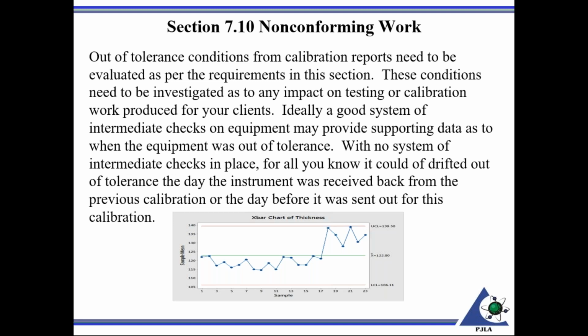for this particular calibration. So perhaps you have a 1 year interval. If you run your equipment checks on a scheduled basis, maybe once a week, perhaps, a good system of intermediate checks. Ideally, these intermediate checks will find perhaps any drifting of your equipment, or it may be able to pinpoint through your past data when exactly the instrument may have drifted out of tolerance.